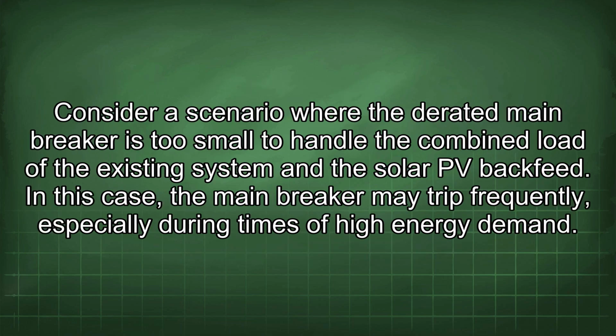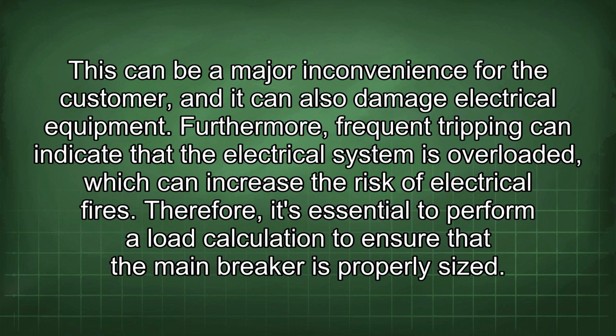Consider a scenario where the derated main breaker is too small to handle the combined load of the existing system and the solar PV backfeed. In this case, the main breaker may trip frequently, especially during times of high energy demand. This can be a major inconvenience for the customer, and it can also damage electrical equipment. Furthermore, frequent tripping can indicate that the electrical system is overloaded, which can increase the risk of electrical fires. Therefore, it's essential to perform a load calculation to ensure that the main breaker is properly sized.